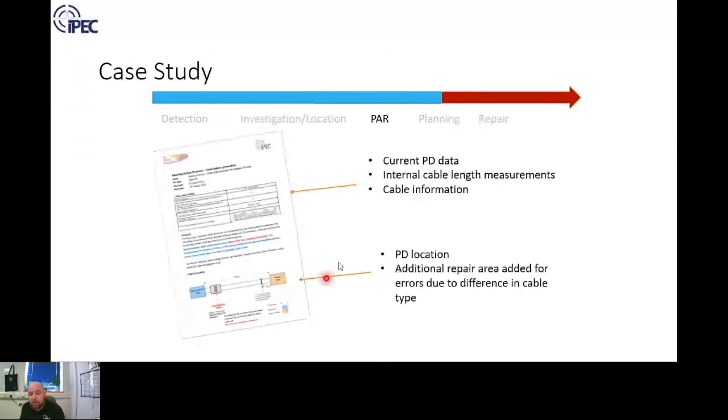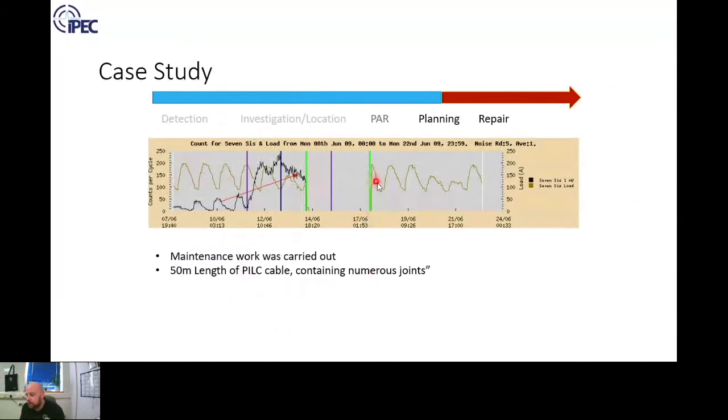This is the load information. Remember, customer takes a shutdown, cable gets back on load, the PD has disappeared. That's just a nice example of how practically it works in practice - the bits that IPEC do and the bits that the customer does. It depends upon who we're working with. Quite often in London, for example, we will do the detection with the monitoring system, we'll do the PD location, issue the report to the customer, and then the customer conducts the repair.